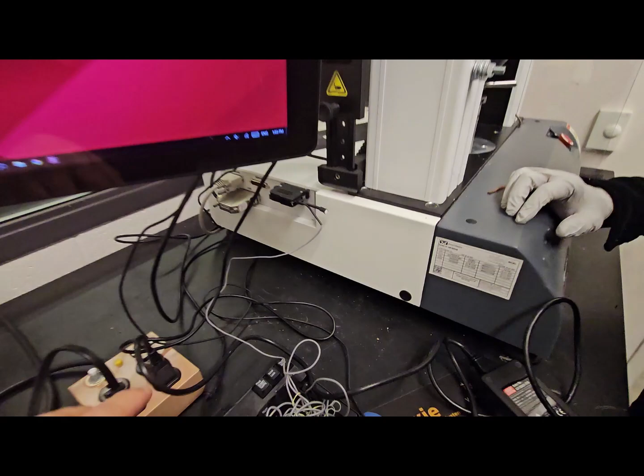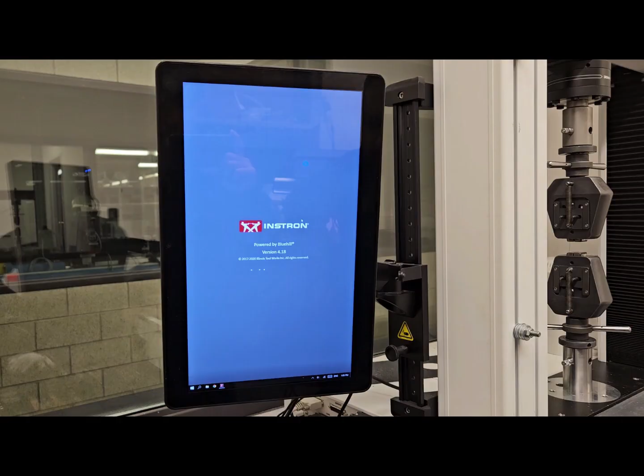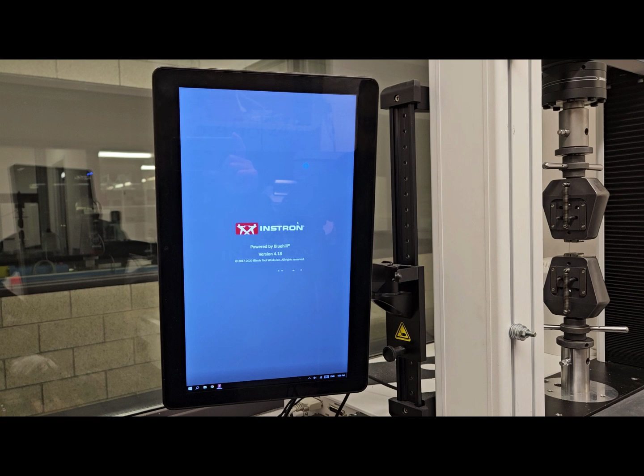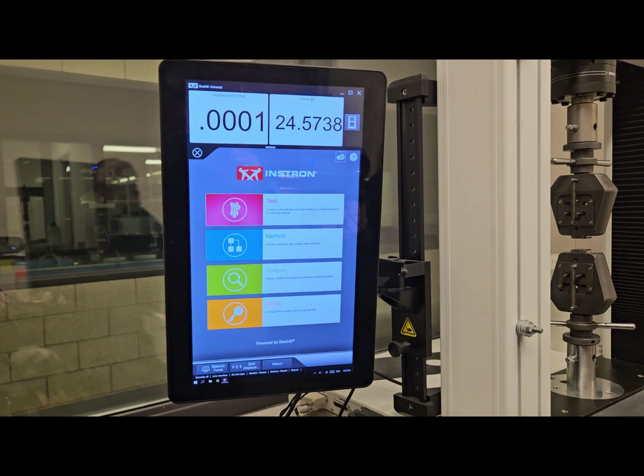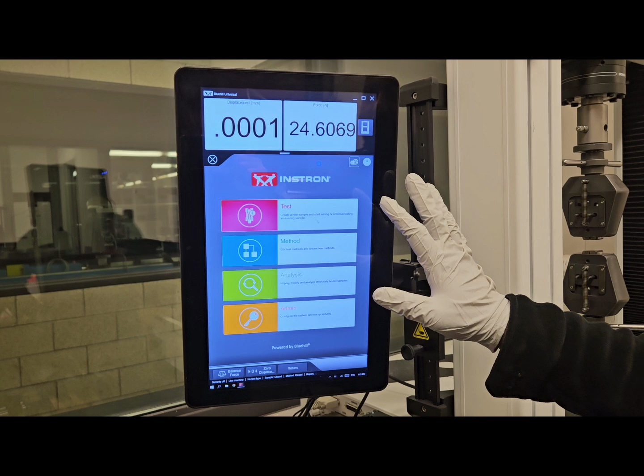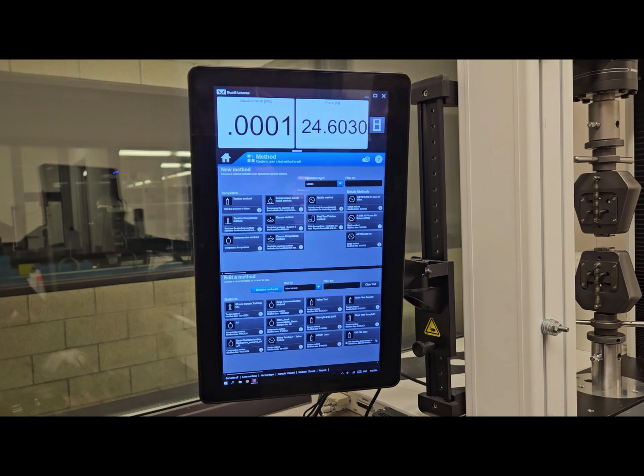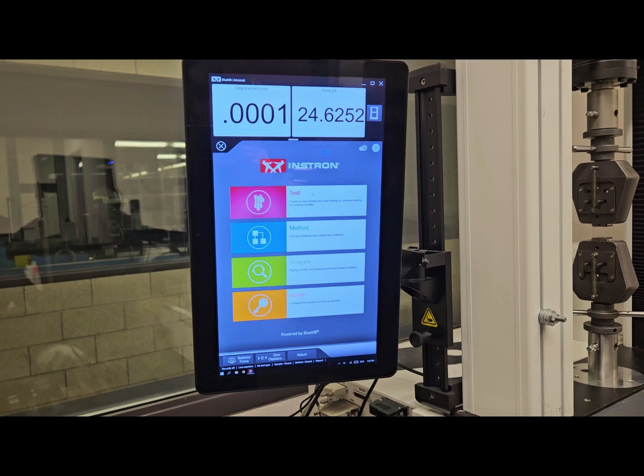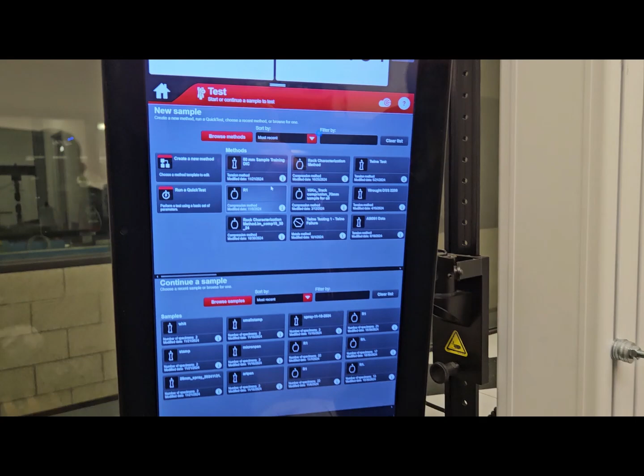Once it is done, the extensometer is now connected over here, and now we need to use this Bluehill Universal software. Once this is open, you can see with this Blue Hill universal software, it shows different sections: test, method, analysis, and admin. For that you need to use this test method. If we are using the previous samples, we need to use that particular program, or if we need to create a new program, we need to click it over here.